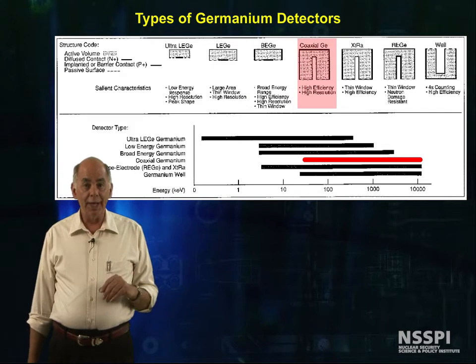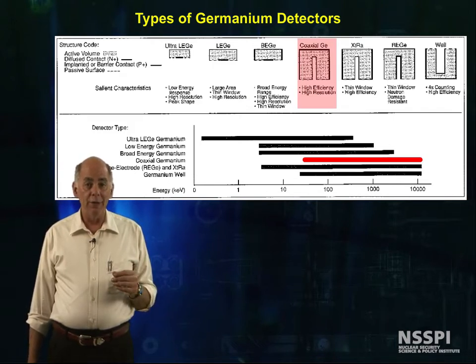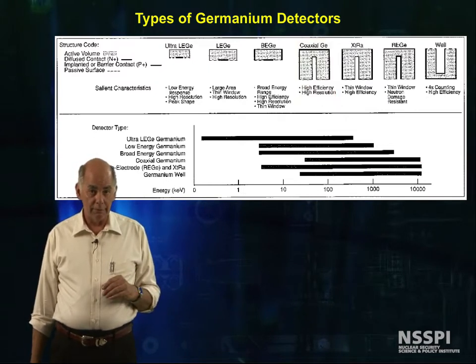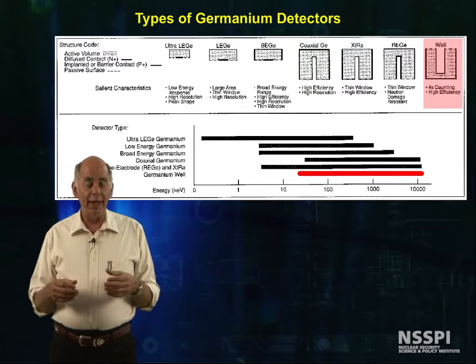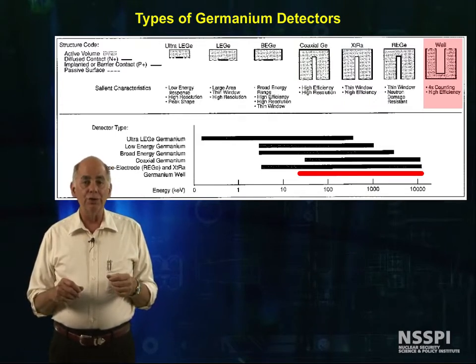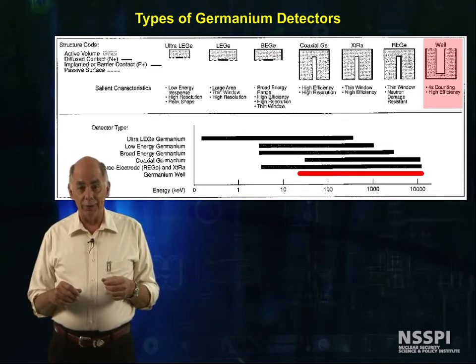Coaxial detectors give a lot of volume, but have a relatively large dead region at the surface, so they're only good for photons 50 keV and above. Well-type detectors are built with an inner well that holds small samples so that you can have almost a 4-pi geometry.